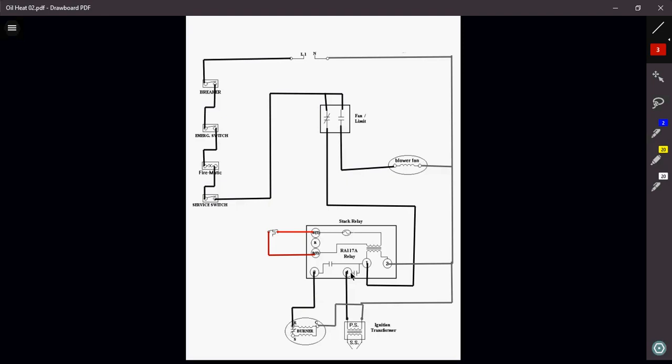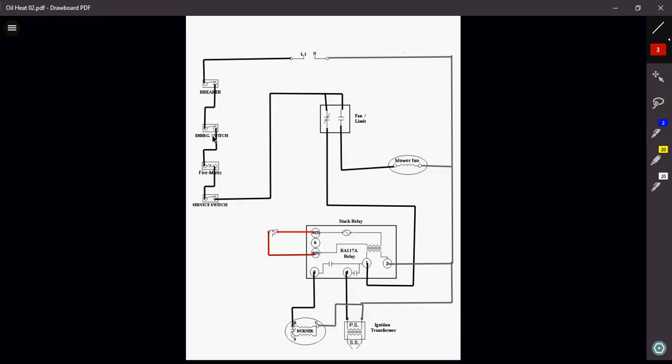So really, the sequence of operation for the stack relay. Now remember, the stack relay has a safety timing of around 90 seconds. So, we have all of our switches closed. So breaker is going to be on, closed. Emergency switch at the top of stairs is going to be closed. Firematic switch is going to be closed. Service switch is going to be closed. So that's going to send power up to my fan limit switch. Which will in turn, because this is a normally closed switch, is going to send power down to my primary control, powering up my transformer.